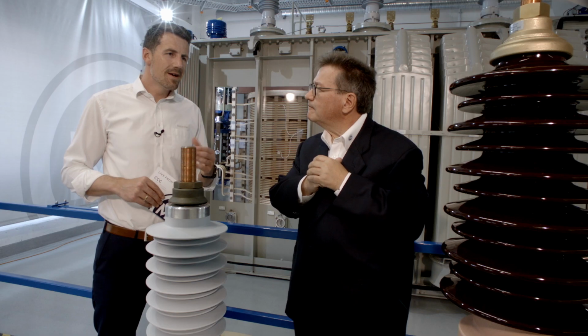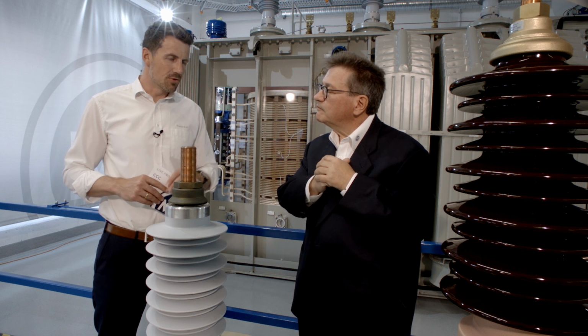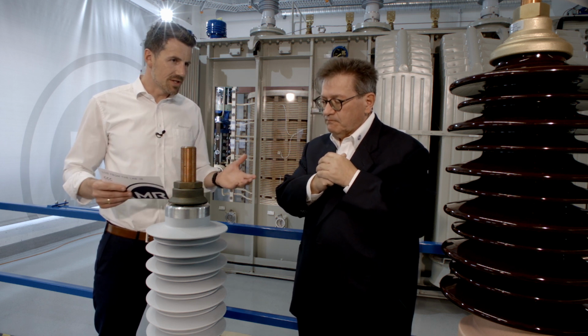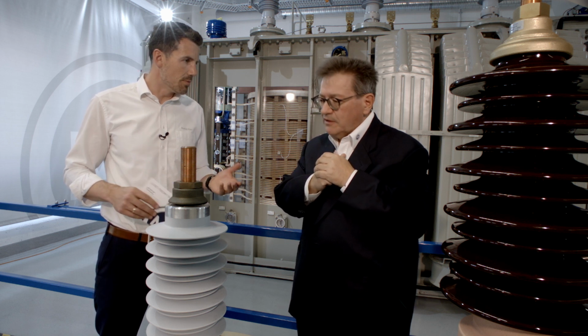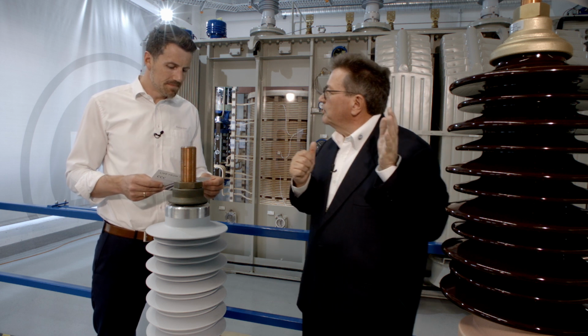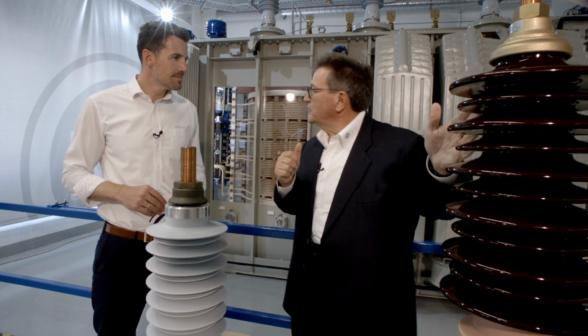But porcelain has at least two problems. One is that it has very low strength as far as cantilever load is concerned, so the bending strength is quite low. And on top of that, porcelain insulator is fragile. It can easily be cracked. It can easily be damaged, even in operation. Okay, that means if a porcelain bushing is pre-damaged, it's just a question of time until it becomes a failure. Sure. Whenever there's a crack in the porcelain, we may have an electrical flashover.